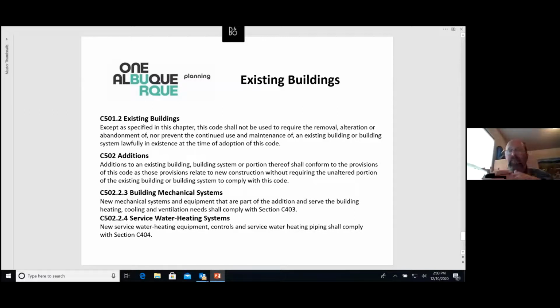So where it talks about existing buildings, and Land touched on some of this. This code isn't intended to require you to change things, abandon them, remove them, if you're not doing anything to it. If you're adding an addition, the addition needs to conform to the provisions of the code. The existing unaltered portion doesn't need to be brought up to the current code. It's in existence, it was to code then, it's still to code, much like everything else we do.